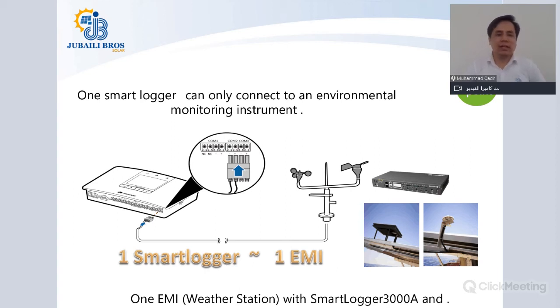One smart logger can only connect to one environmental monitoring instrument. Normally the weather stations come with an analog to digital converter, I mean the RS485 converter, which connects directly to the smart logger or at the end of the chain of a solar PV inverter. You can only connect one weather station, and with one weather station you can still get the performance ratio. You can install one weather station with our smart logger 3000A, which is normally used in most of the projects that we supply inverters to.